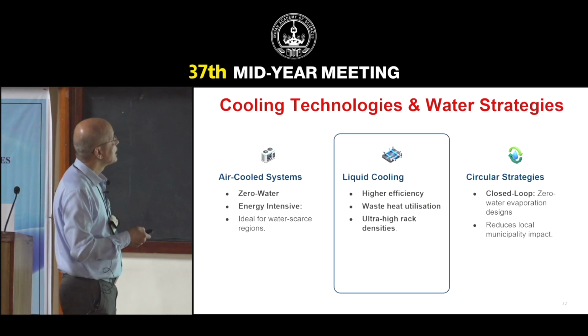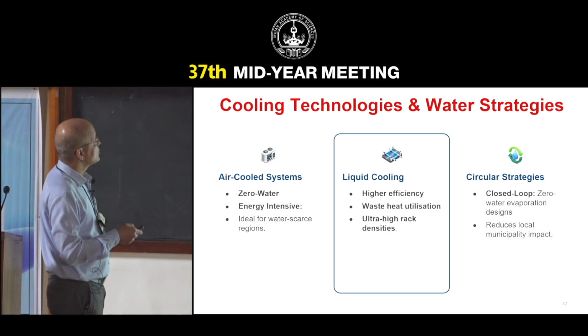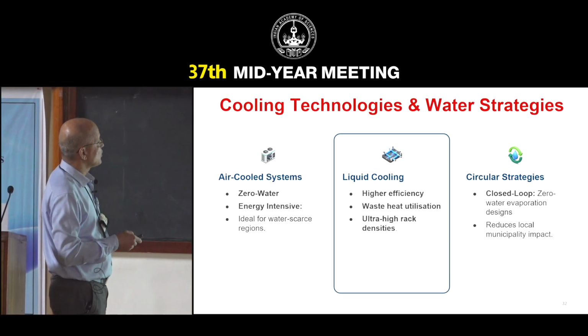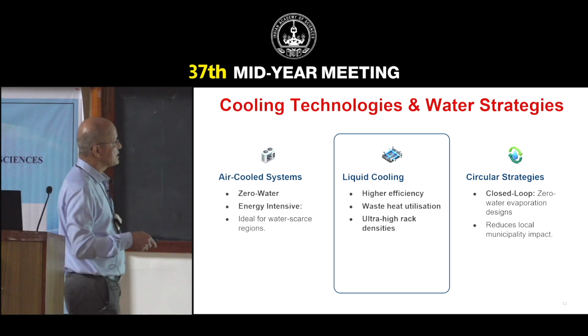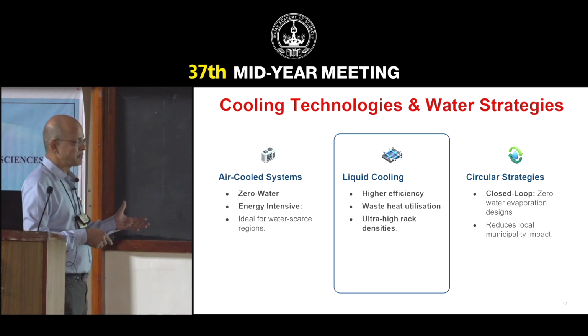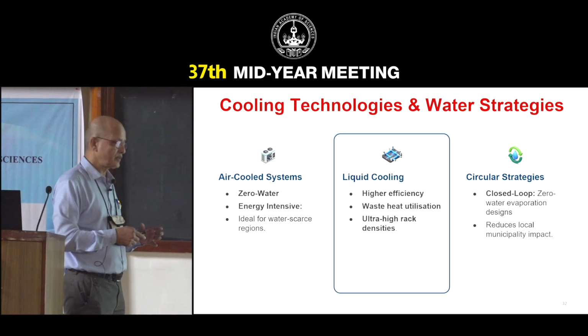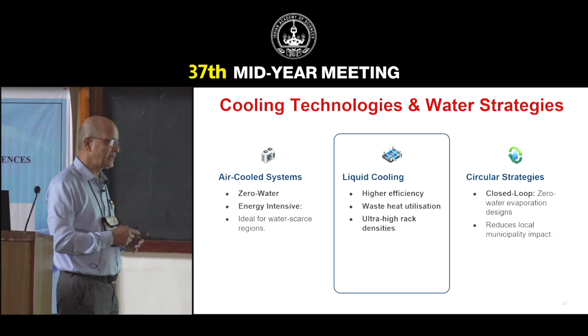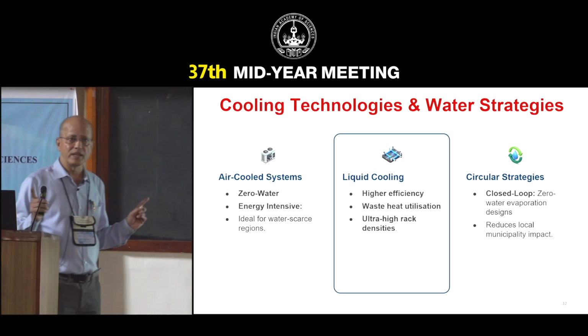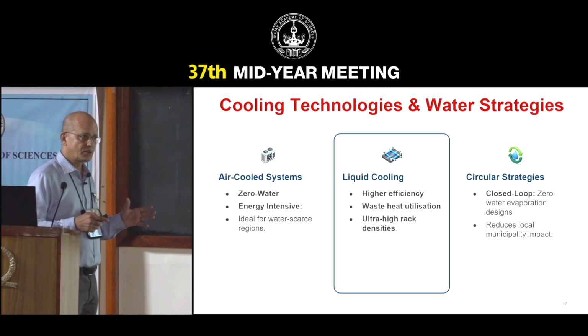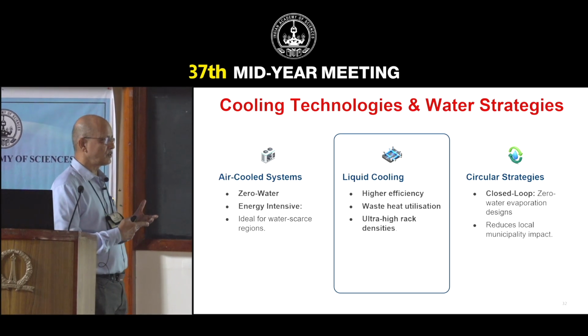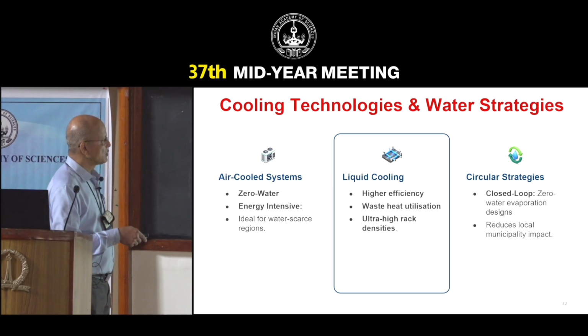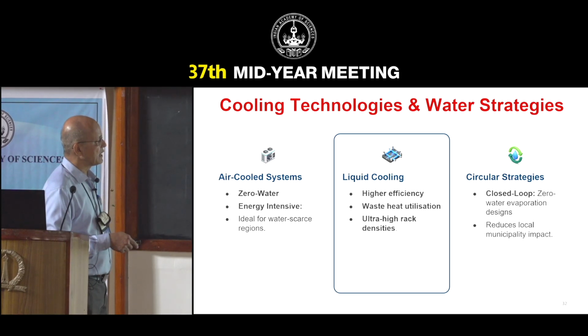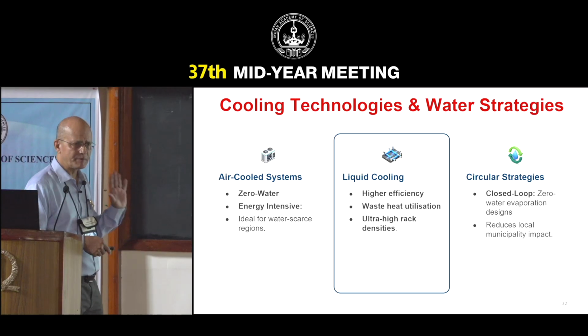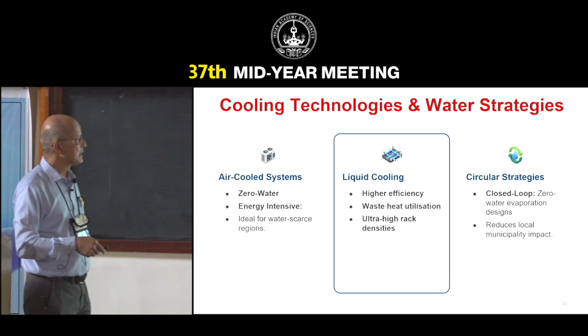In the cooling technologies and water strategies, there are air-cooled systems where zero water will be required, but air-cooled systems don't use evaporative cooling, so you need a huge footprint of cooling if it's a dry cooler. That amounts to real estate and also other capital expenditure. So liquid cooling is more preferred, and water cooling, especially for the cooling tower, is preferred. Water consumption is something which is unavoidable at the moment.